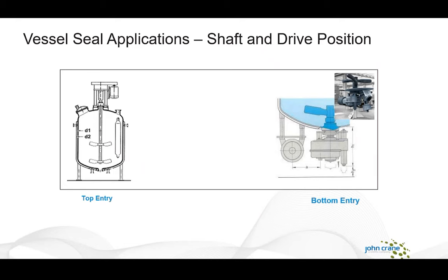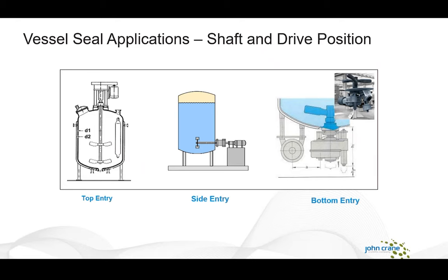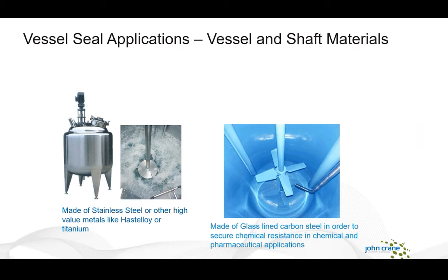With top entry applications the fluid in the vessel never actually touches the seal, so the seal must be purposely designed to withstand dry running conditions. Our third type is the side entry seal — the drive system is supported on a pedestal and we fit the seal in the housing, which then protrudes into the vessel. John Crane supplies vessel seals in materials compatible with the vessel construction, whether stainless steel, Hastelloy, or titanium.